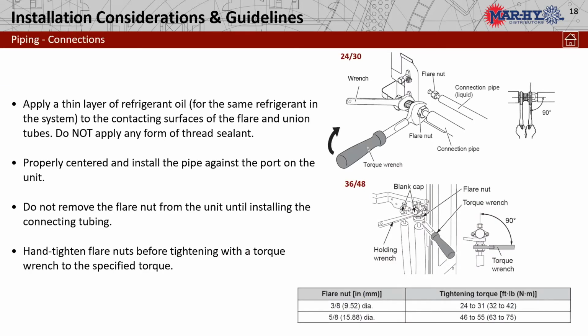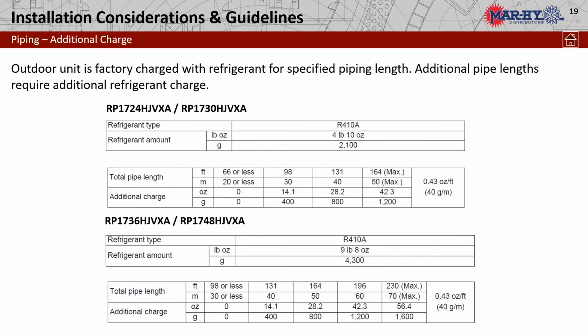Now the guidelines for connections, these are all flared connections, indoor and outdoor. So we're going to do our typical refrigeration practices that we would do with our minis. There again, we're going to do a nice ream job on the copper. We're going to flare it. Make sure you put your nut on first. Flare it. Put a thin layer of oil on front and back of the flared surface, and then we will torque it to specs. As well as that, we will do our common practices as pressure testing, make sure it holds, check for any leaks, and then we will do our evac down to 500 microns, letting it hold for 30 minutes, and then we can go ahead and open up the refrigerant ports.